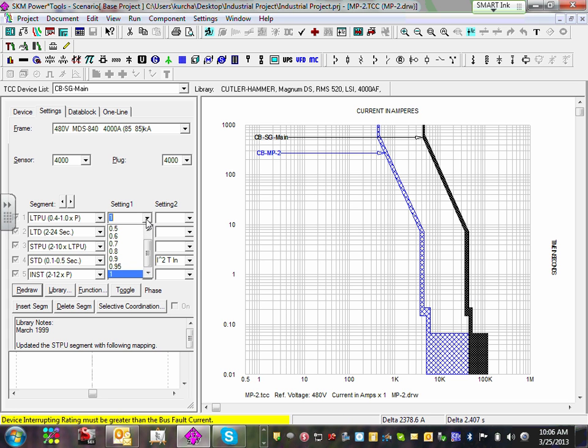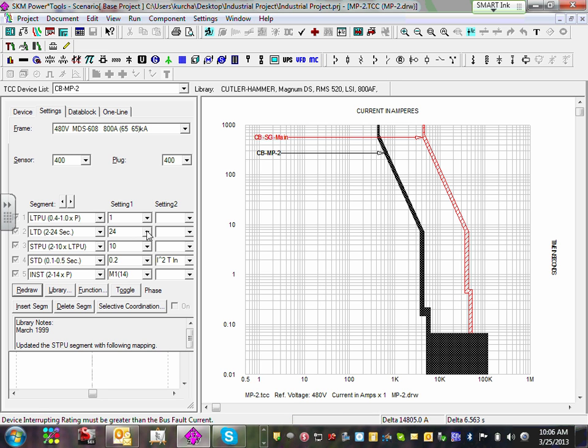Or you can come over here and put this at 1, then go here and put this one at the highest, and go to the short time pickup, make it the highest, and make sure this one also sits at the highest. Everybody sits there. Circuit breaker gets the highest. The main circuit breaker is the highest. The same thing for the main of the panel. Make sure your main is set at the highest, right in here. You can do them from right in here, the highest settings, and your instantaneous setting the highest settings. You got yourself the highest settings for all of them.